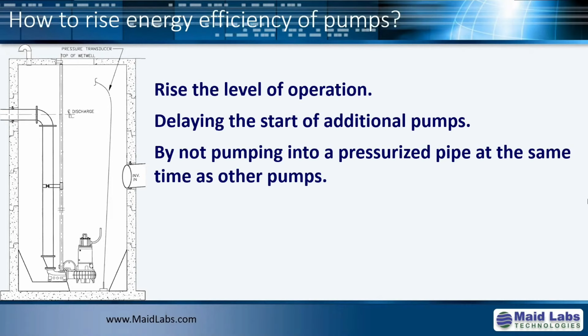So the idea behind increasing the efficiency of a pump station is very simple. Raise the level of operation of your pumps when it's safe to do so. Delay the start of an additional pump for as long as possible when it's safe to do so, and try not to pump into a pressurized pipe at the same time as other pumps, if you can do that. Okay, and for that you really need a good SCADA system to do it. So that's the basic idea behind it.